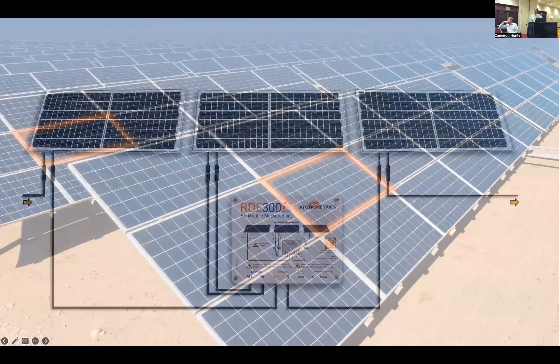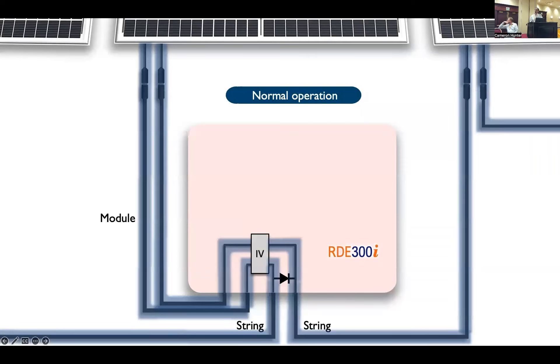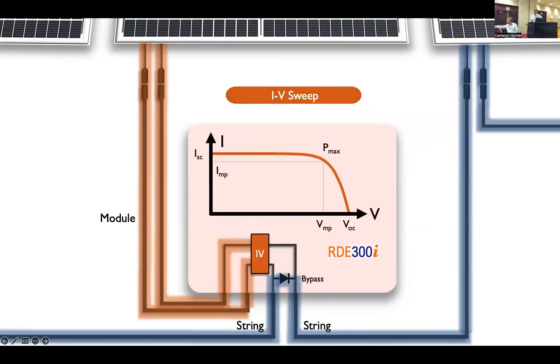How does it work? You're going to take the module that you want to have this continuous measurement on and wire it to the rest of the array going through the IV measurement equipment. Here I'm showing our new product, RDE300i. During normal operation, your test module is going to be connected to the rest of the string through the IV measurement equipment and current will be flowing as shown in blue normally. So the module is contributing to power production.